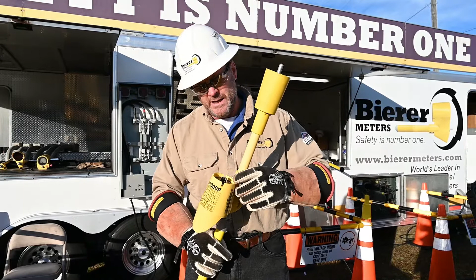There are 2 reasons why we're going to test first on that conductor knowing it's energized. By doing so, we're actually testing the tester on a live known voltage source, before we open.